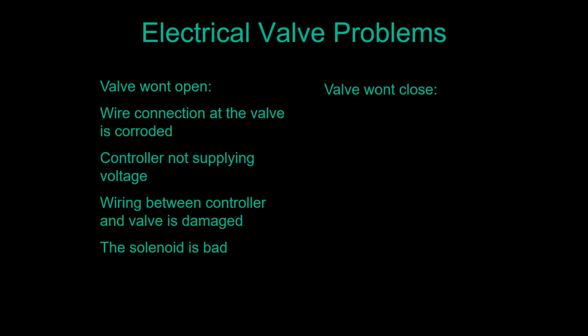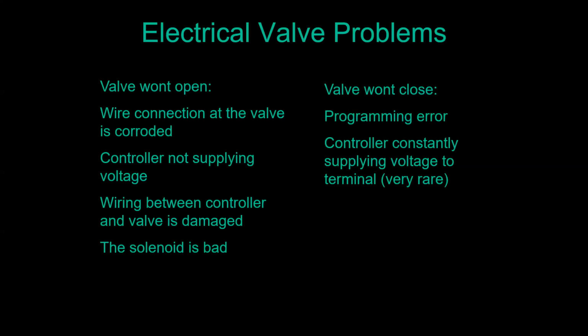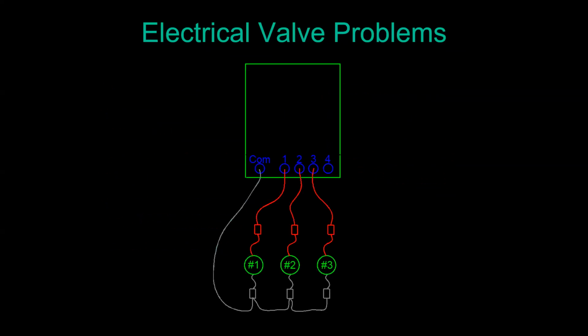If the valve won't close and it's electrical, it's a programming error. It could be a failure of the controller on the other side, where even though the controller is not running, it's still sending voltage to that terminal. It's very rare, but it can happen. So here we've got a diagram of what that wiring looks like.